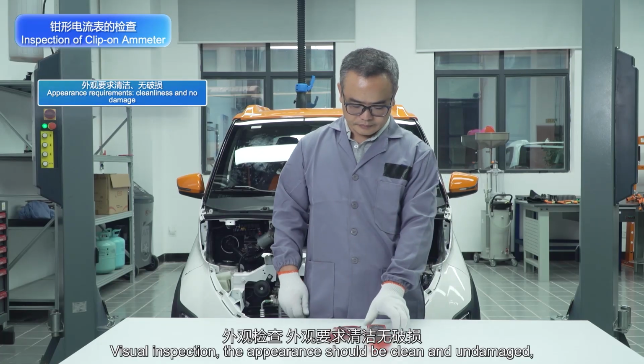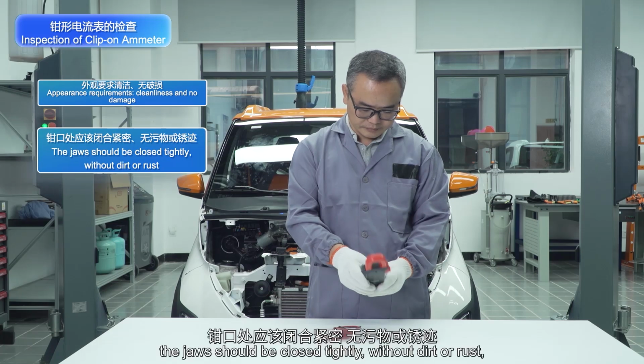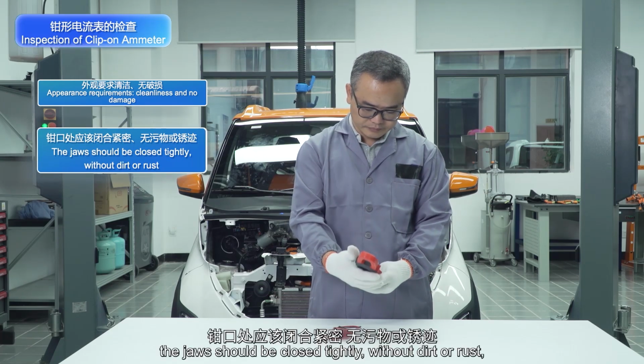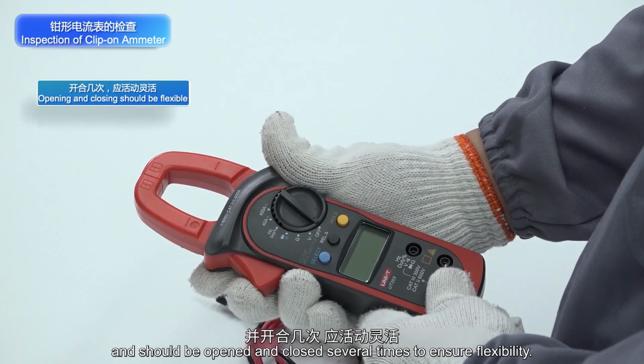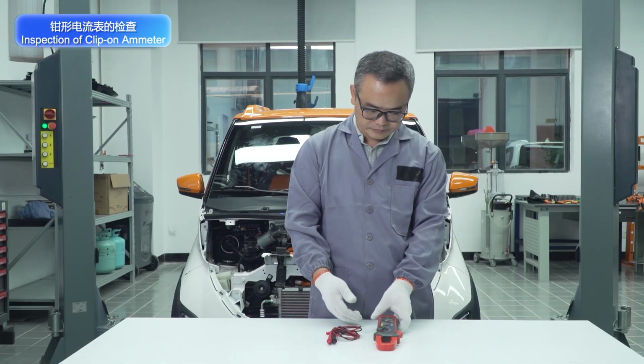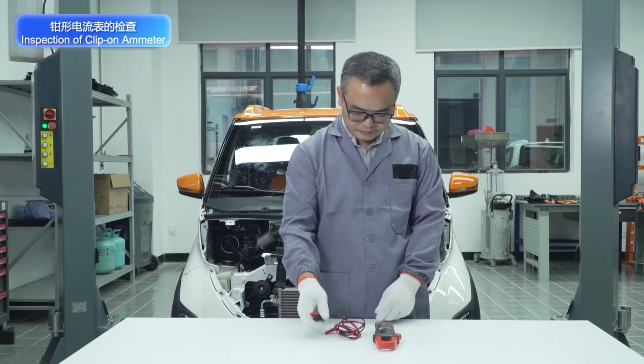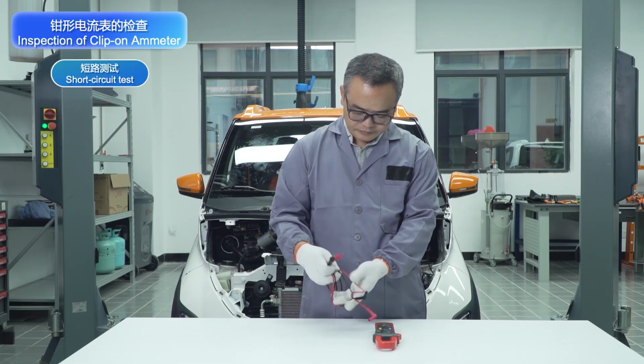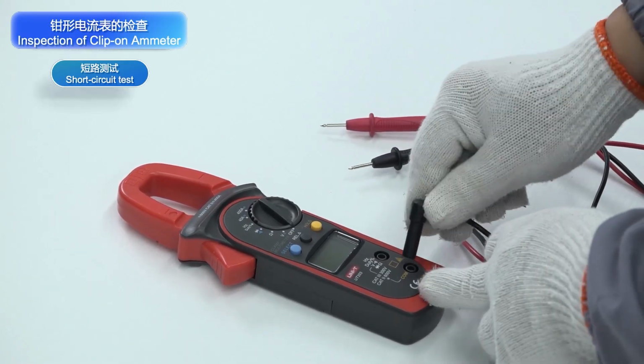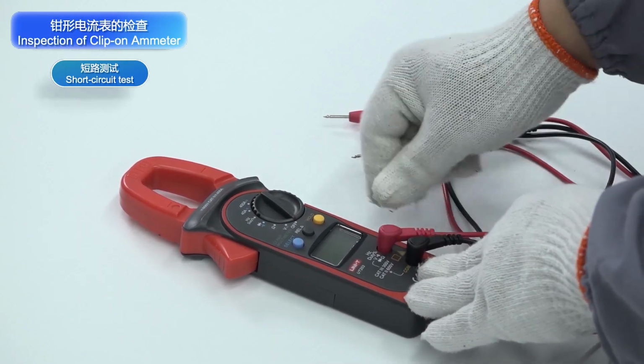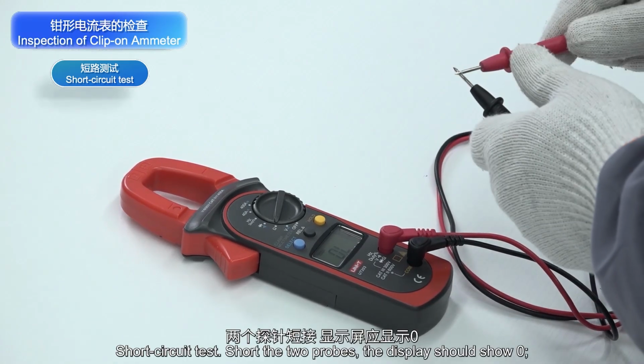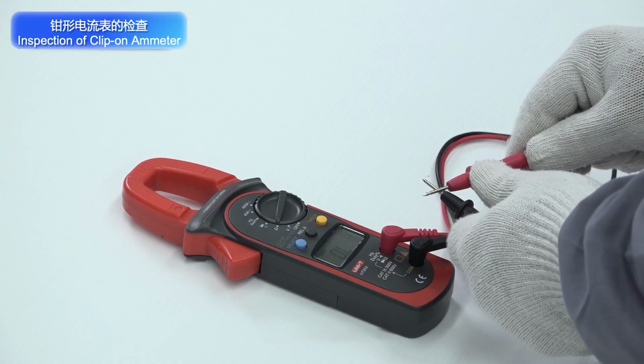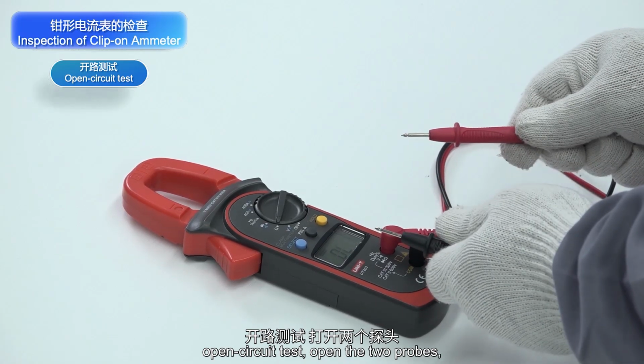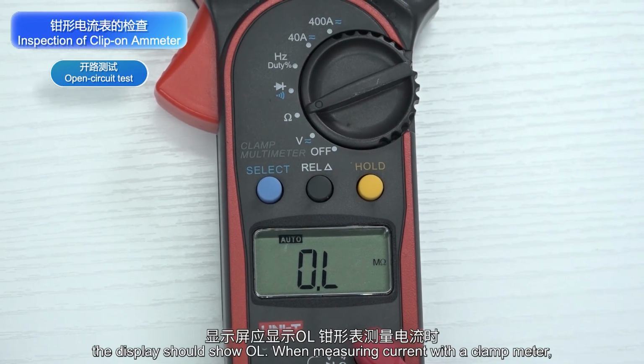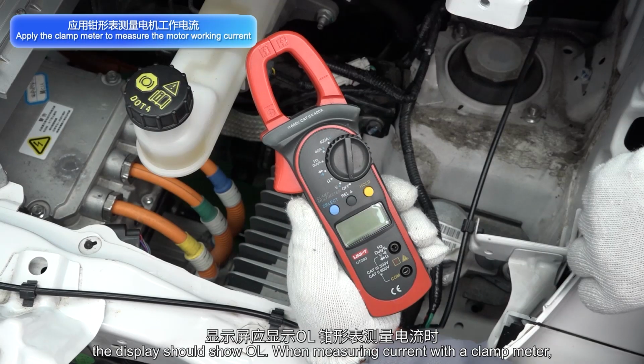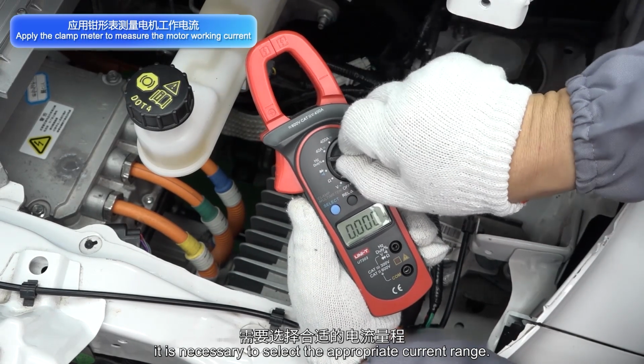Visual inspection: the appearance should be clean and undamaged. The jaws should be closed tightly, without dirt or rust, and should be opened and closed several times to ensure flexibility. Short circuit test. Short the two probes, the display should show 0. Open circuit test, open the two probes, the display should show OL. When measuring current with a clamp meter, it is necessary to select the appropriate current range.